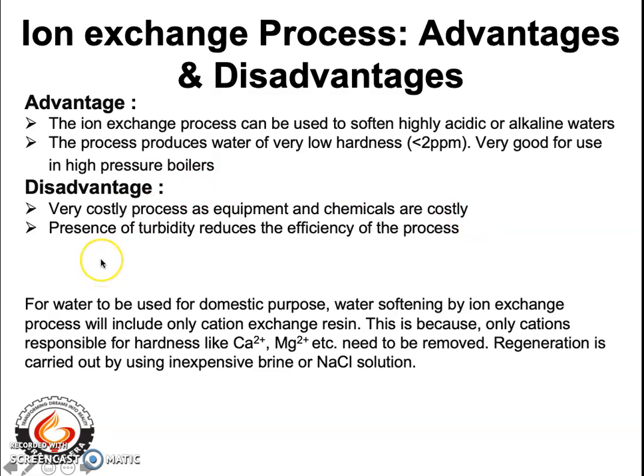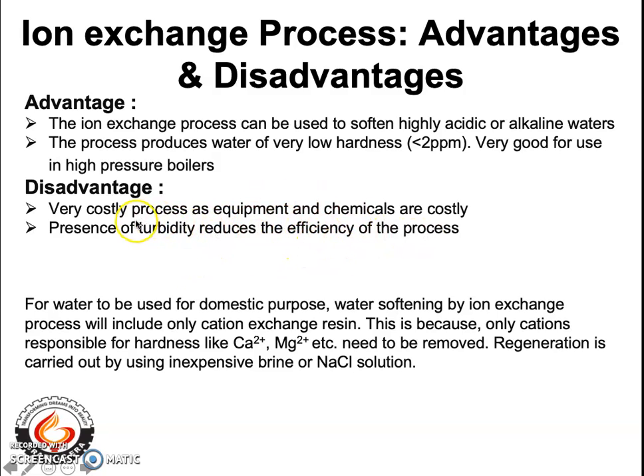Another disadvantage is that if the hard water contains suspended particles in addition to calcium and magnesium ions, the water needs to be pre-treated prior to its entry into the resins. If we do not pre-treat it, the turbid water can reduce the efficiency of the process and can also destroy the resins. So an initial pre-treatment prior to the ion exchange process is required.